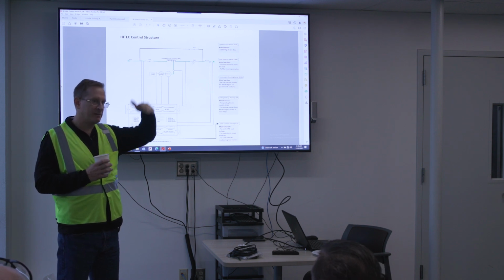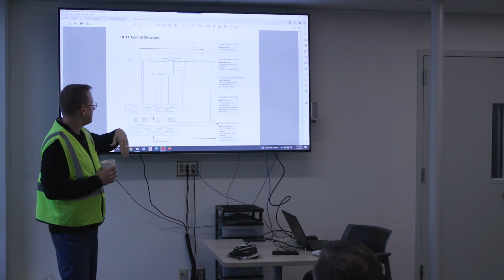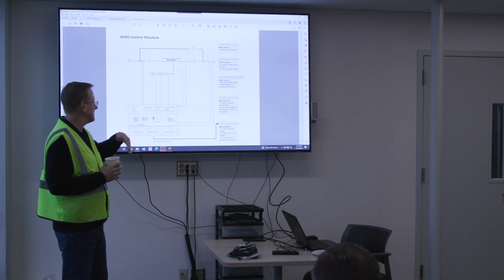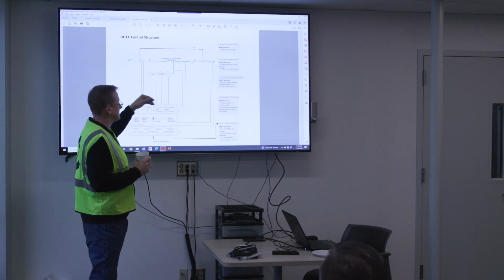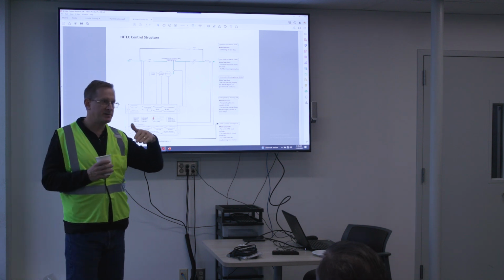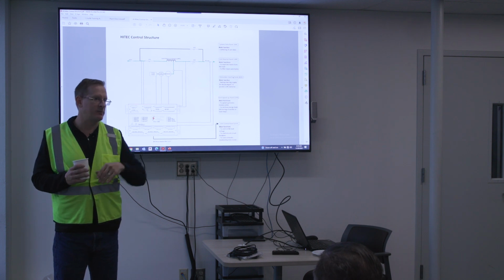So you must have some loads that come on or off that affect your voltage. But I noticed that sometimes it'll vary throughout the day. And what our Dicon can actually do is, if that mains voltage comes down a little bit, it can actually lower voltage so that we match the utility voltage a little bit better, rather than staying at a constant 4160.